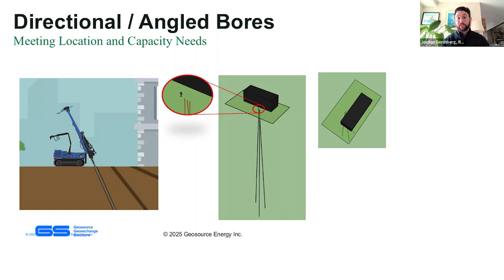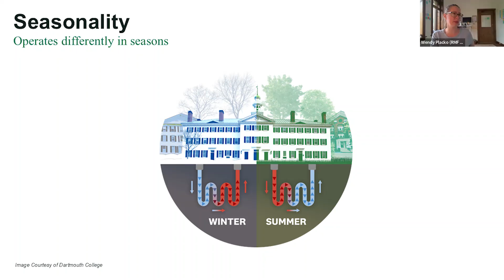Great point. I want to touch for a moment on seasonality, to reinforce the concept that a geo-exchange bore field can be both a heat source and a heat sink. This type of graphic can be helpful to introduce someone to how it behaves differently in the different seasons. In winter, we draw upon the heat we stored, and in summer, we deposit the heat left over from our cooling load. So this is something you can have in your arsenal when describing this to clients.